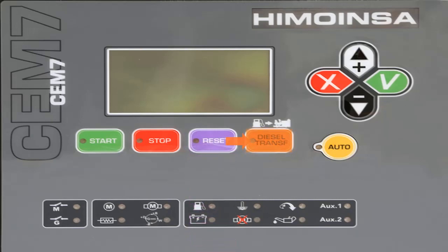The fuel transfer pump button: when the genset is equipped with an external fuel tank, this button activates the fuel transferring from the external tank to the internal tank. In manual operation, the pump is activated if the fuel level is below the programmed limit. A lit LED indicates that the fuel transfer pump is active.